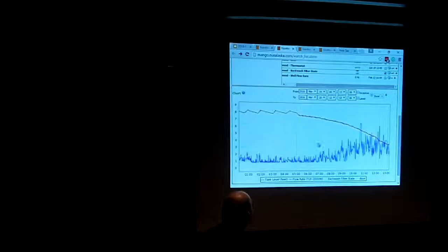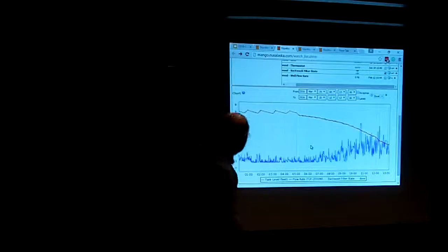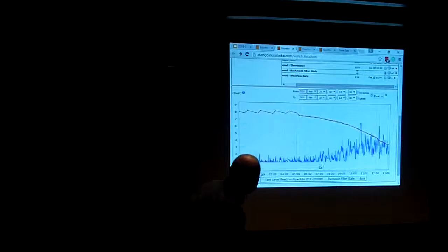So now I can see correlations between my data, and I can begin to look and see, do I need to make a trip out there or not? So blue here is my flow rate, and sure enough, I've got an increase in flow, but I started going out of my normal operation when the flow was down here at minimal flows. So that tells me there is a problem. What also tells me is that my backwash was triggered right then when that all started.